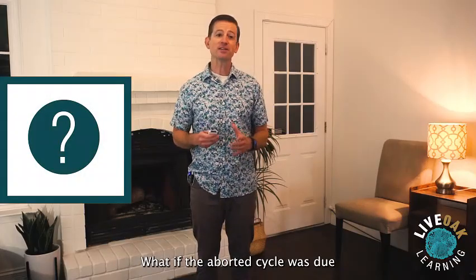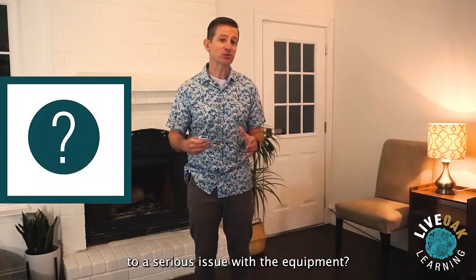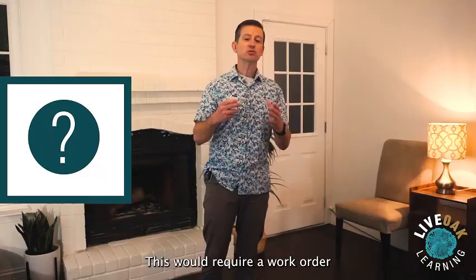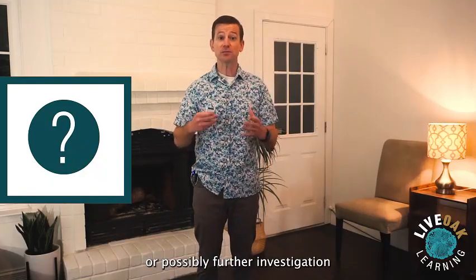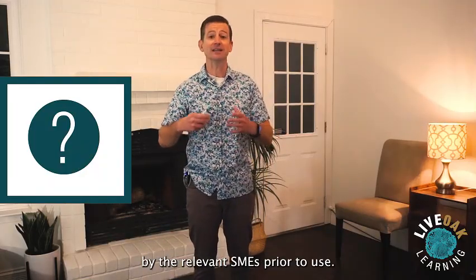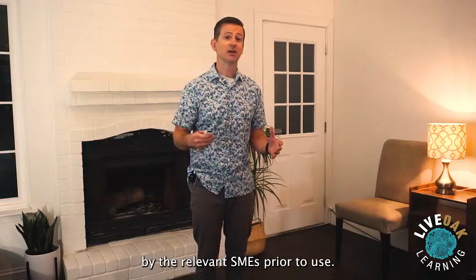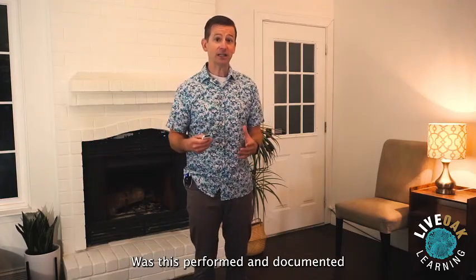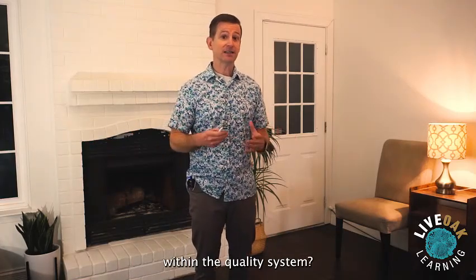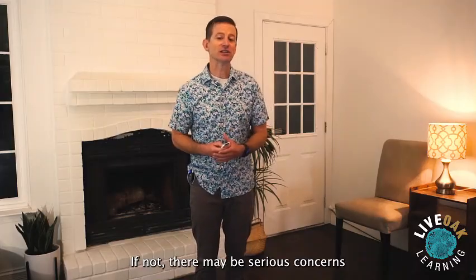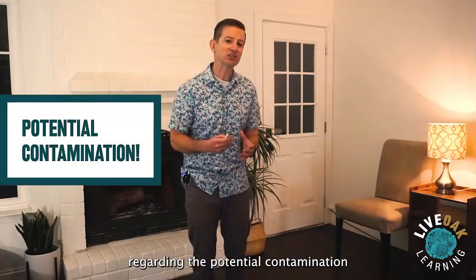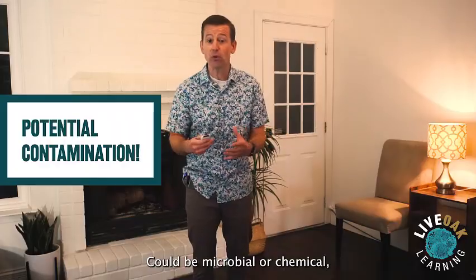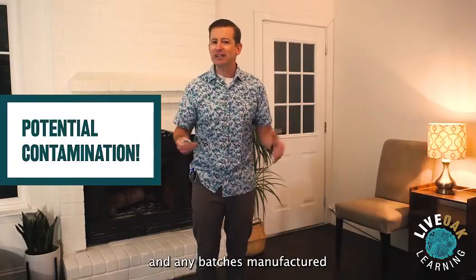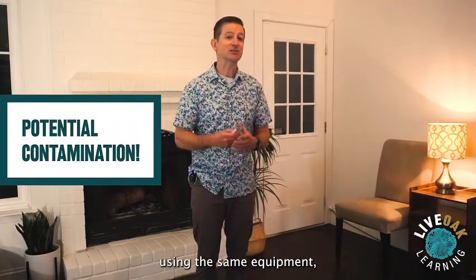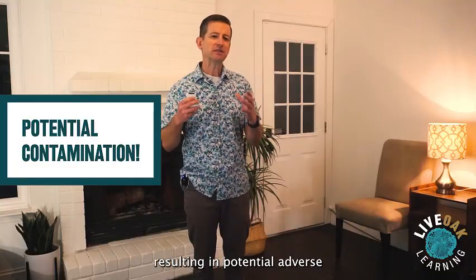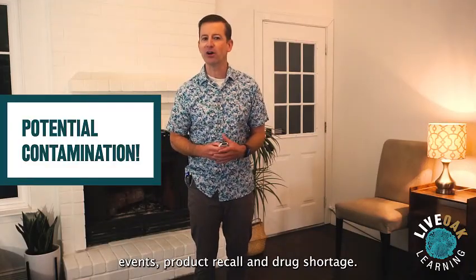What if the aborted cycle was due to a serious issue with the equipment? This would require a work order or possibly further investigation by the relevant SMEs prior to use. Was this performed and documented within the quality system? If not, there may be serious concerns regarding the potential contamination of this batch. Could be microbial or chemical, and any batches manufactured after this event using the same equipment, resulting in potential adverse events, product recall, and drug shortage.